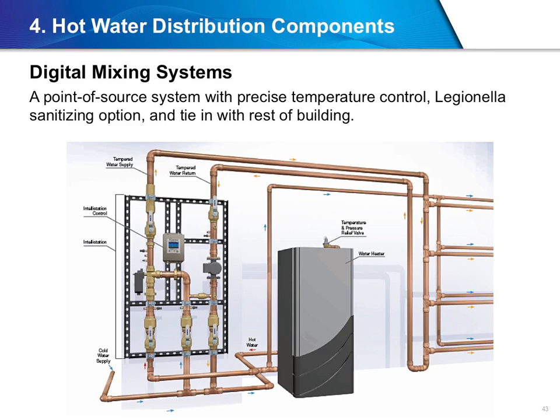At the same time, the digital mixing system can control temperatures leading to faucets, showers, and other outlets to reduce the risk of scalding in the mixed water. If combined with separate point-of-use protection, the digital mixing system allows for continuous elevated circulation temperatures to prevent Legionella per ASHRAE and CDC guidelines.